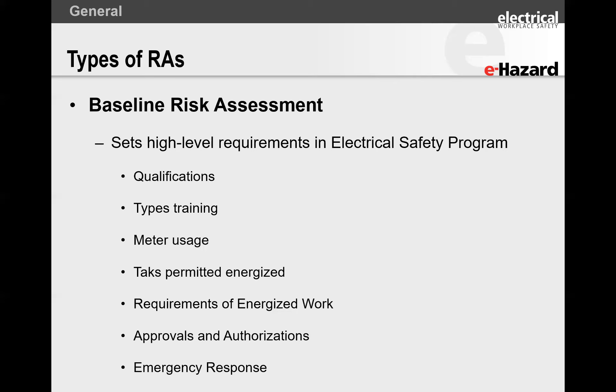You've got to define your classes of workers — class one workers, class A workers, class Z workers — have your different groups of personnel and say this group is going through that training, this group goes through this training. Here is how I am making sure they understand how to use a live line tool. Define your requirements for energized work and your tasks permitted while energized. Your baseline risk assessment is in that written electrical safety program.